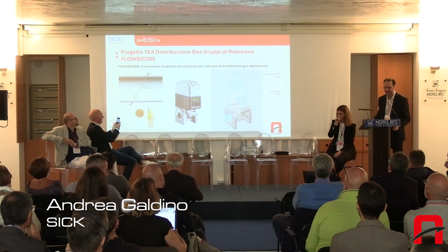I would like to focus on the measurement element that actually carries out the measurements for the flow. The measurement principle is the ultrasound measurer. For those of you who do not know it, that's its simplified version. Two sensors, A and B, exchange data concerning the sound wave. When the flow is stopped, the crossing times of the sound waves are the same.